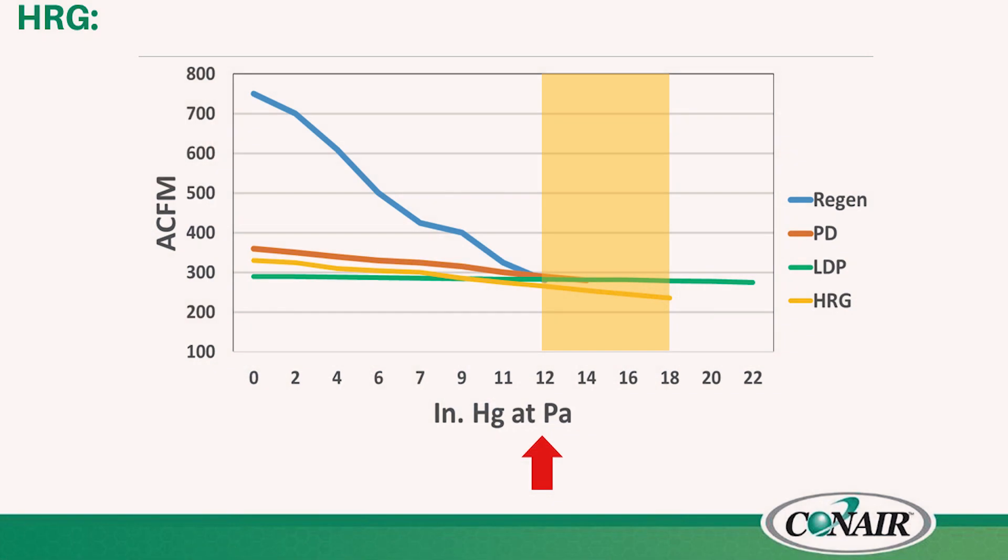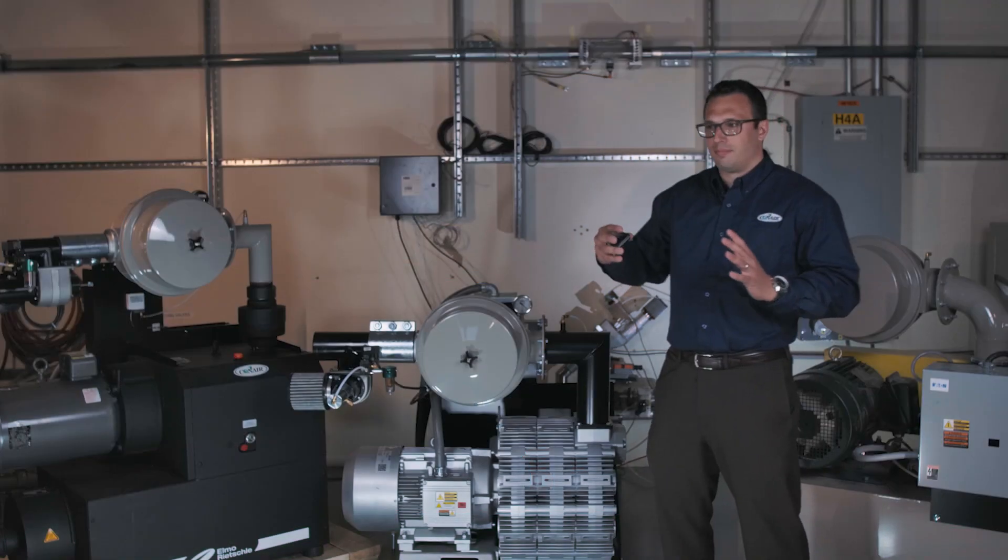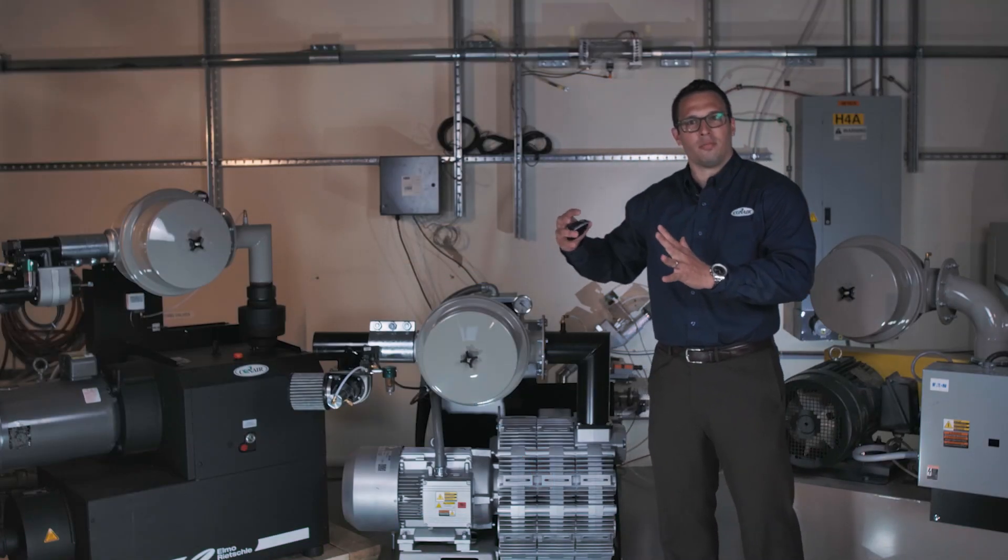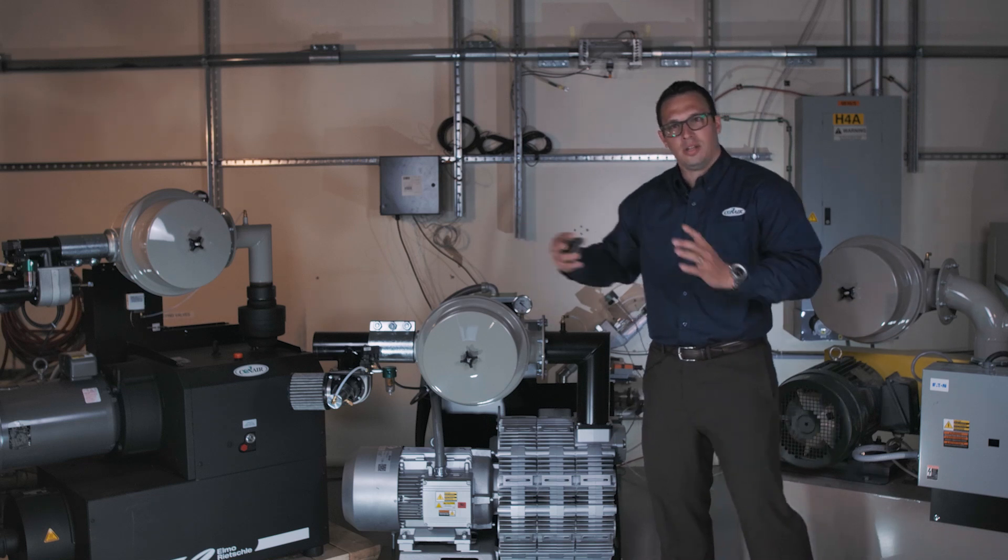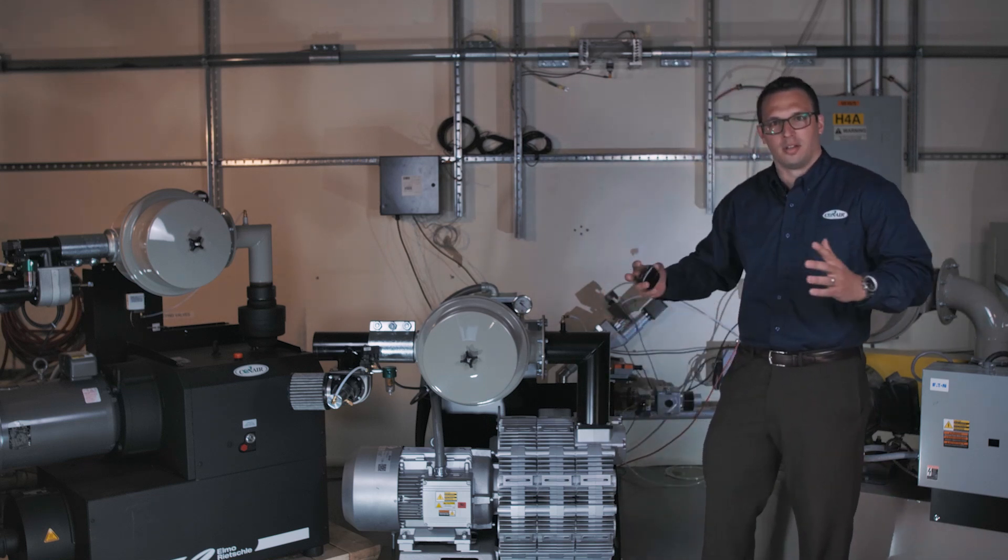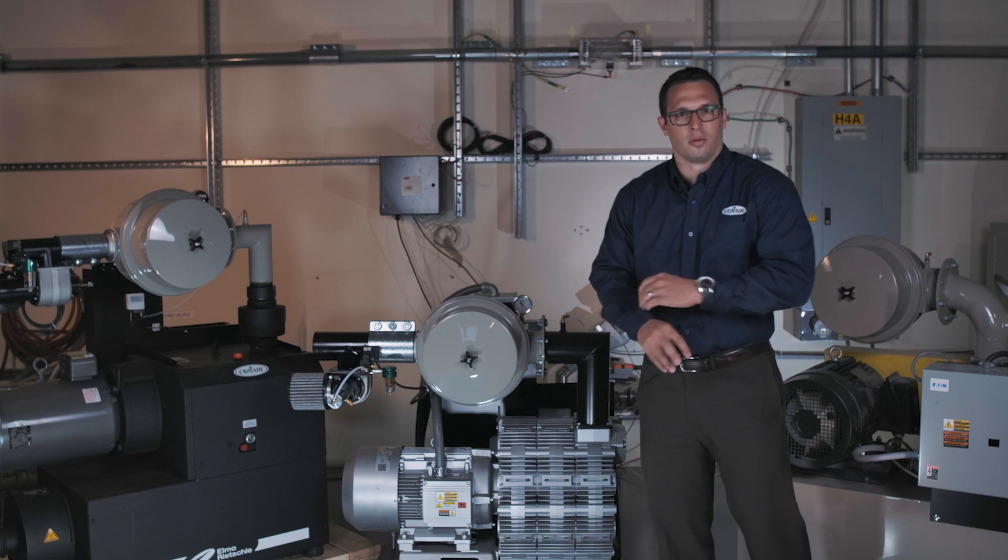Notice how on the curve, the pump curve mirrors the positive displacement pump, but extends now further into that vacuum capability all the way up to 18 inches of mercury, which can handle most, if not 75, maybe 80% of most applications where we typically would have to use the LDP pump for. We now can use this HRG pump, and it's going to be a perfect pump for those applications.